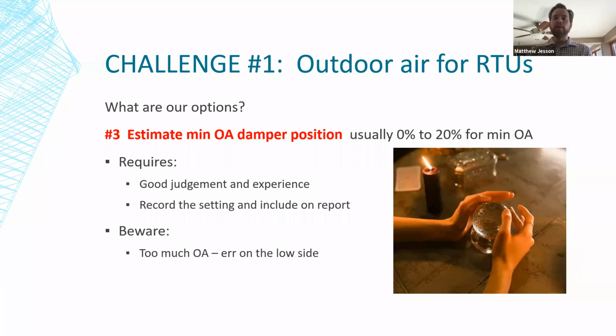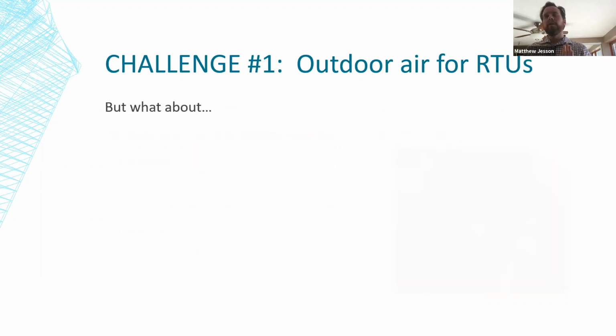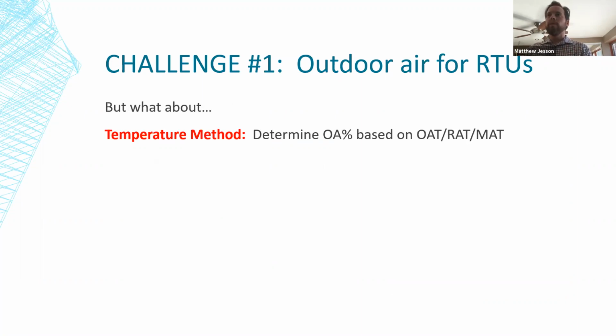Once again, you just got to be careful that you don't bring in too much outdoor air and give yourself temperature problems. Probably best to err on the low side with this method. So you might be thinking, okay, what about this? What about that? A couple other things that usually come up. One is the temperature method. You can calculate your percentage of outdoor air based on comparison of the outdoor air, return air, and mixed air temperatures. And that's totally valid.